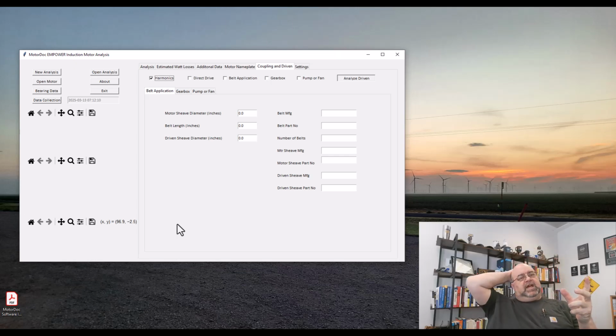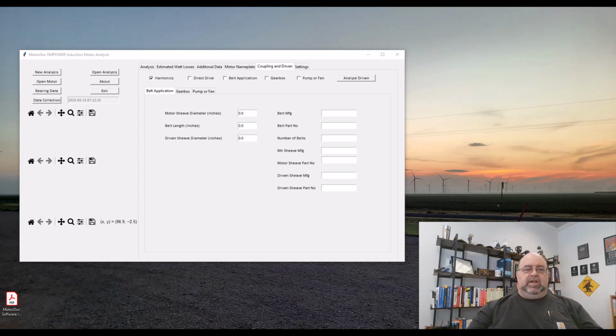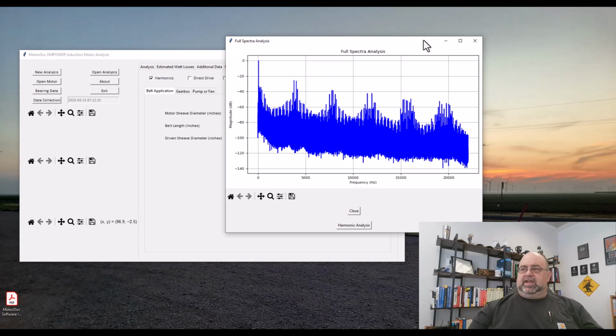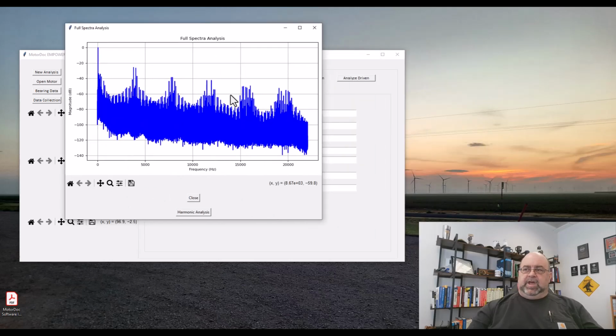So the next one we'll do is what I was doing with putting the current clamp against the side of the machine. This is what it commonly looks like on the output of a VFD out to 22 kilohertz. You can see a combination of harmonics, even and odd, all the way out to 22 kilohertz, and the relative force in decibels is pretty high all the way out, and it would go further if I read further out.